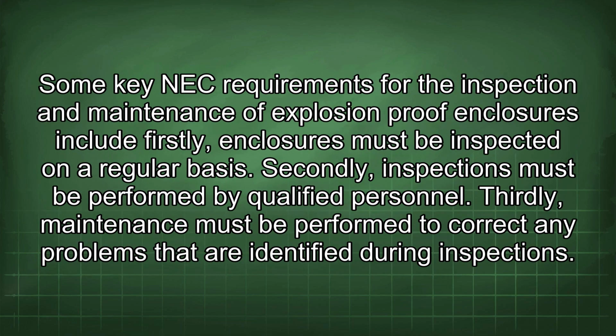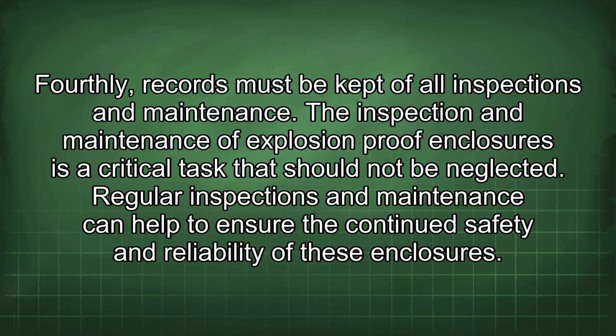Some key NEC requirements for the inspection and maintenance of explosion-proof enclosures include: firstly, enclosures must be inspected on a regular basis. Secondly, inspections must be performed by qualified personnel. Thirdly, maintenance must be performed to correct any problems that are identified during inspections. Fourthly, records must be kept of all inspections and maintenance.